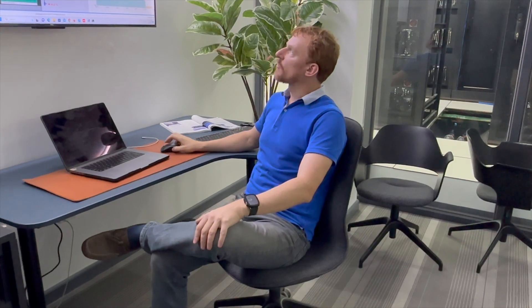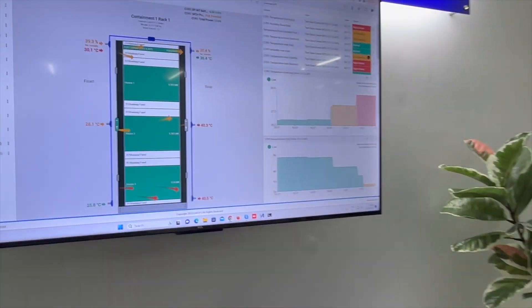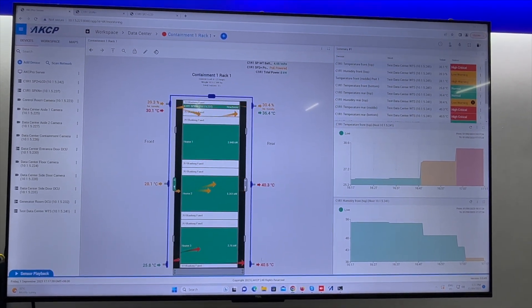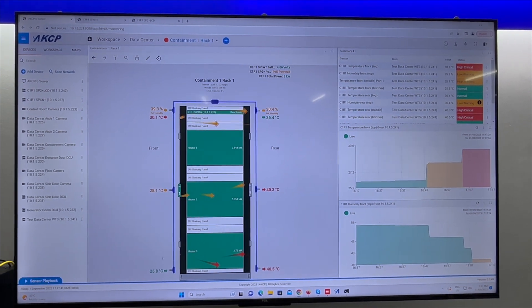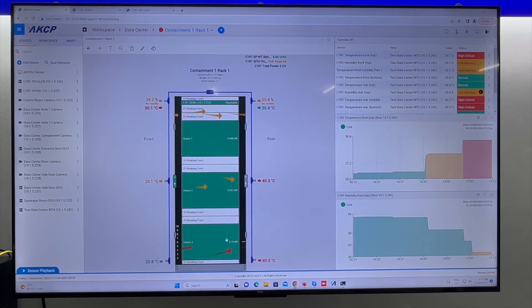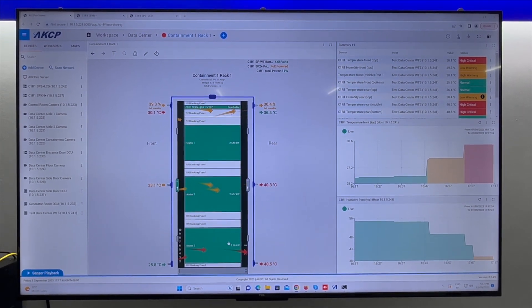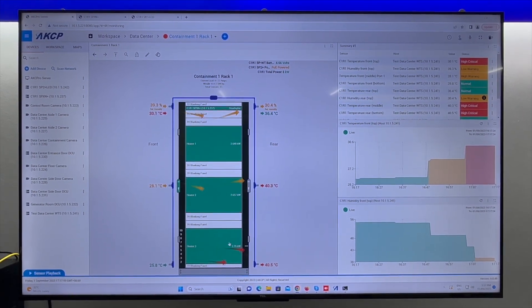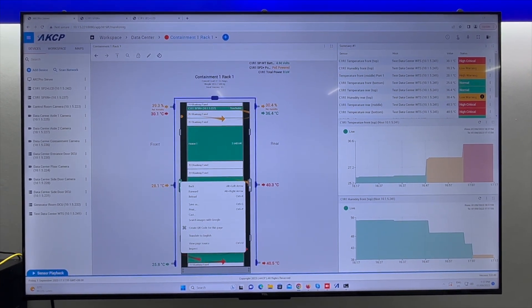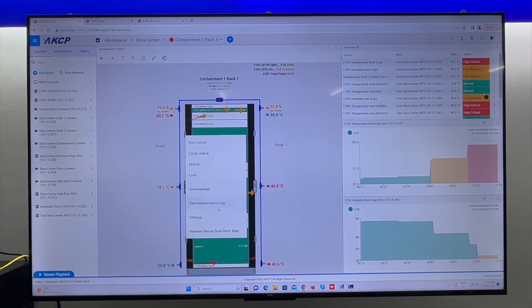Here in the control room we're bringing all the data back and displaying it in AKCP Pro Server. I've already configured one rack — this is the rack we've already got operational. You can see the rack outlet temperatures, inlet temperatures, and each of the heaters mounted inside the rack. We've basically created a digital twin of everything in the data center, and we've got our swing handle locks that we can lock and unlock from the user interface here.